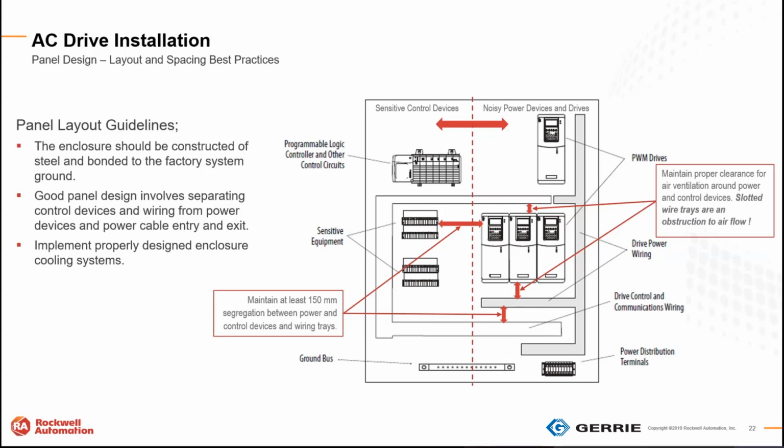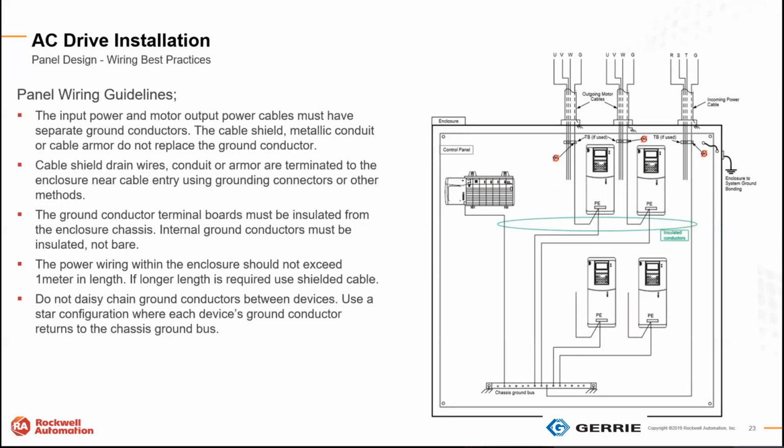The PowerFlex 520s now need 2 inches above and below. You might think that doesn't sound like much, but we run into a lot of installations where we don't have that clearance, and we're running into heating problems. Just because the Panduit or the wire trays are slotted doesn't necessarily mean we're getting proper ventilation. We can attest to that. A lot of customers put that Panduit very close to the drive and don't allow for that 2 inches of clearance, and we do have heating problems and effects that come back to haunt us.